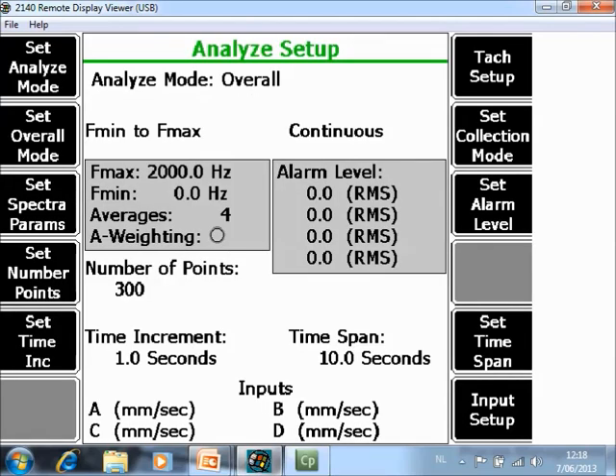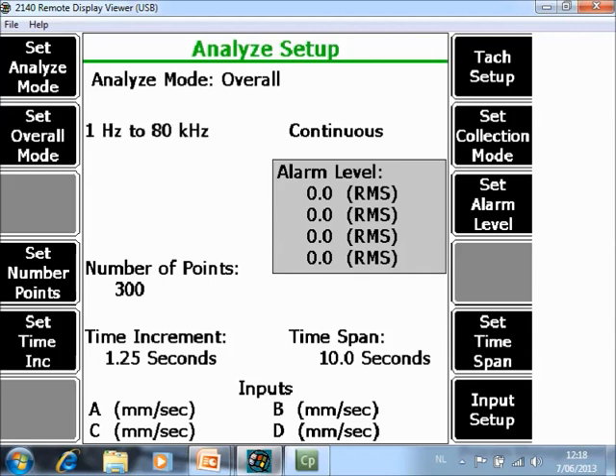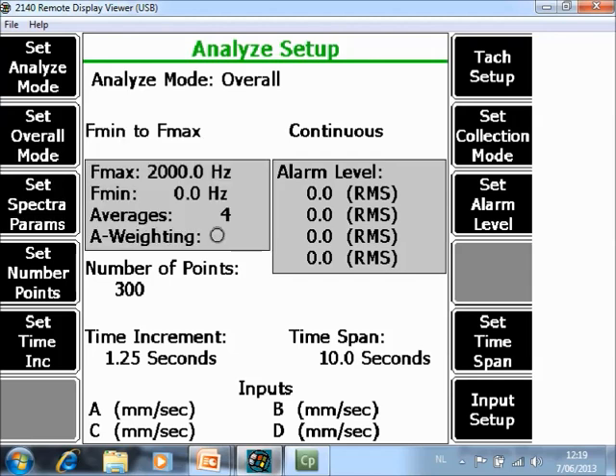F2 Set Overall Mode has two different modes. The 1-80 kHz means it will measure the full frequency range of the analyzer and calculate the overall from the full frequency range, or you can specify manually an Fmin and an Fmax.